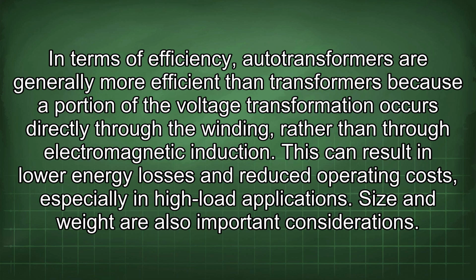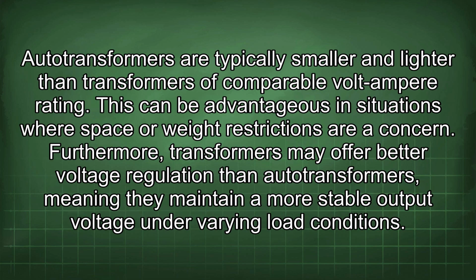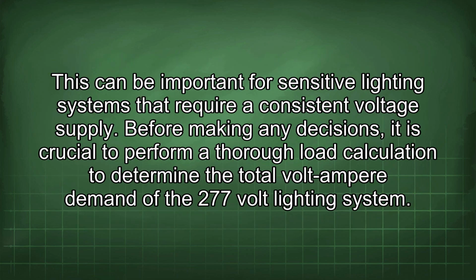Size and weight are also important considerations. Autotransformers are typically smaller and lighter than transformers of comparable volt-ampere rating. This can be advantageous in situations where space or weight restrictions are a concern. Furthermore, transformers may offer better voltage regulation than autotransformers, meaning they maintain a more stable output voltage under varying load conditions. This can be important for sensitive lighting systems that require a consistent voltage supply.